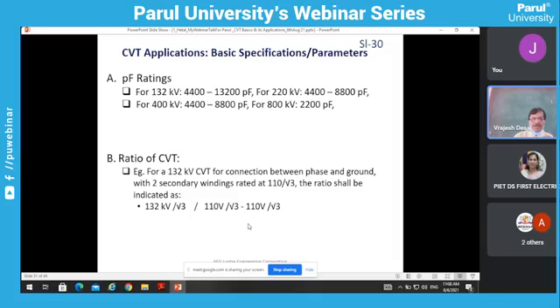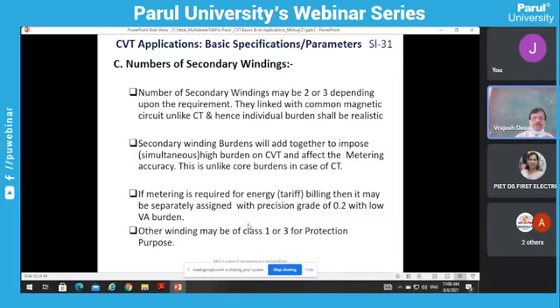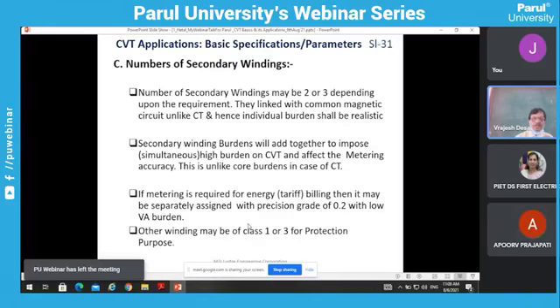If you have two windings, then there will be another such winding. And if it is three windings, then there will be three such voltages available for meters as well as relays. As we are talking about the number of secondary windings, mainly we have two to three. The first is for metering purpose, the other two are for protection purpose. So normally this intermediate PT is provided with three windings, right?